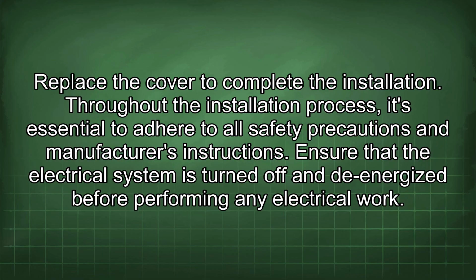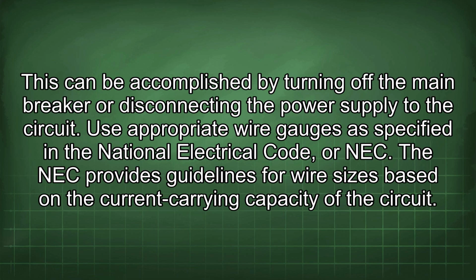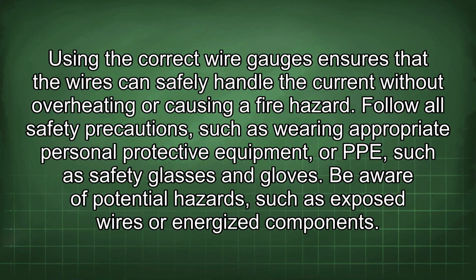Ensure that the electrical system is turned off and de-energized before performing any electrical work. This can be accomplished by turning off the main breaker or disconnecting the power supply to the circuit. Use appropriate wire gauges as specified in the National Electrical Code, or NEC. The NEC provides guidelines for wire sizes based on the current carrying capacity of the circuit. Using the correct wire gauges ensures that the wires can safely handle the current without overheating or causing a fire hazard.